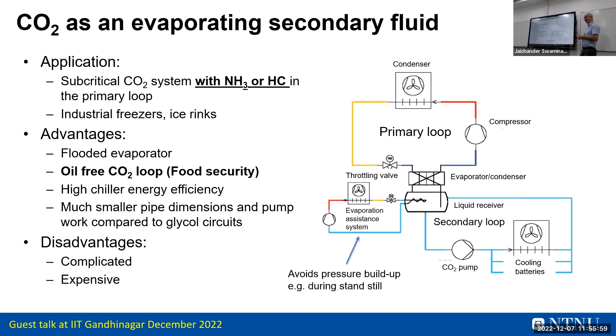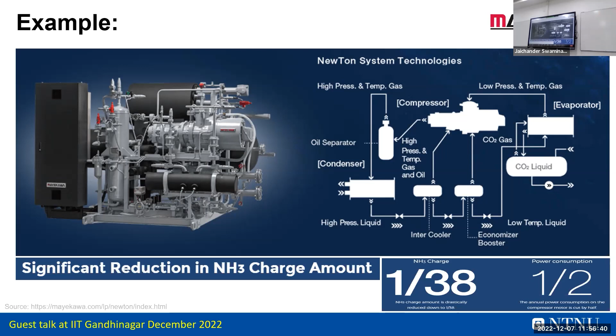Or we can look at this one in the market from Japan, where they use ammonia as I just showed you, and pump the CO2 for factories, or even ice rinks and so on. The ammonia is very compact in the middle, a very low charge, because they also have an indirect system towards the heat rejection or heating up of the secondary loop. So the charge is much reduced, and it's half the power.